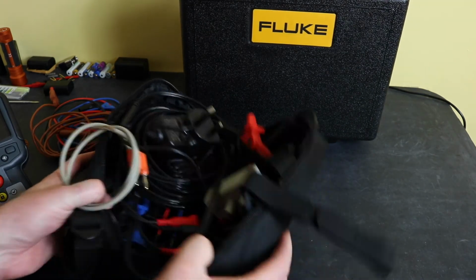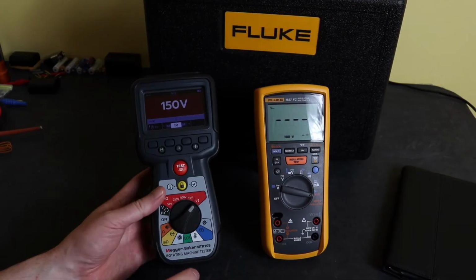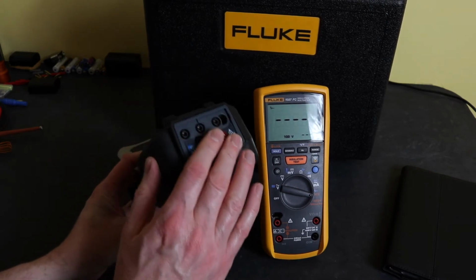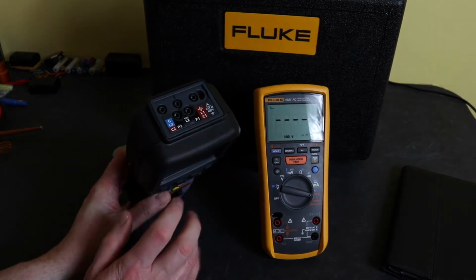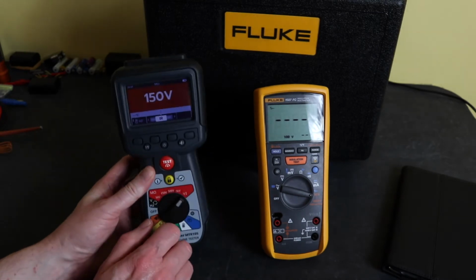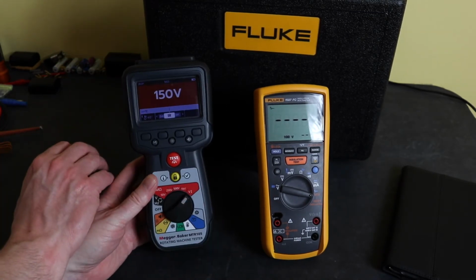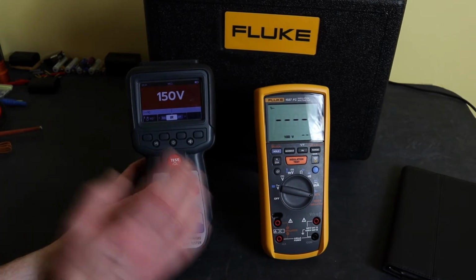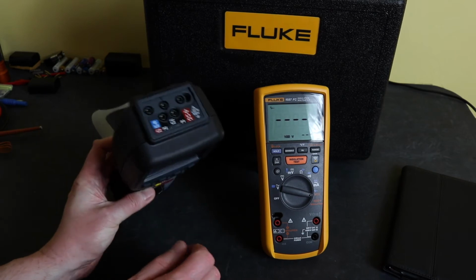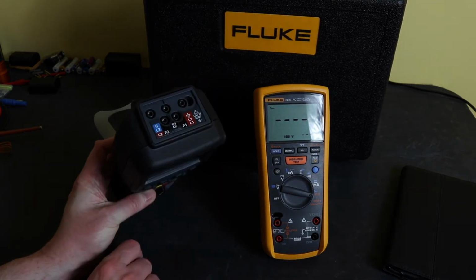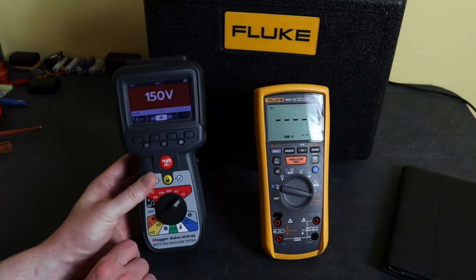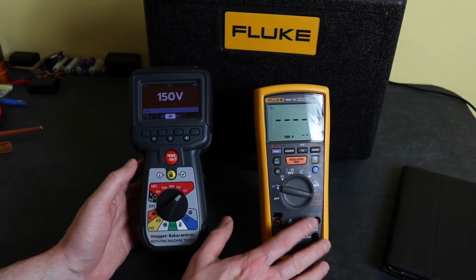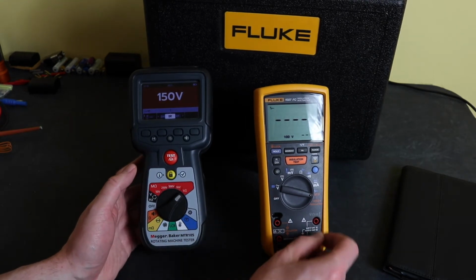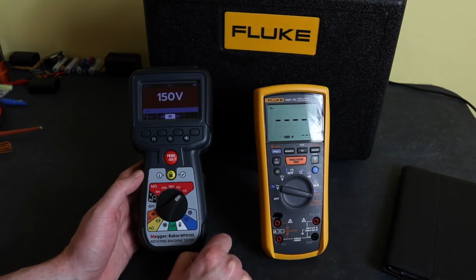Okay, so we'll chuck this out of the way and take a closer look at the instruments. In terms of connections on the instrument, all the connections are made at the top here on the MTR105, which does keep leads out of the way when you're testing. However, because of the multifunctionality of this, you quite often find you have to bring the meter around to select where to put the probes, whereas with the Fluke, everything is slap bang in front of you and you can swap them over as you sit here and look at the instrument.